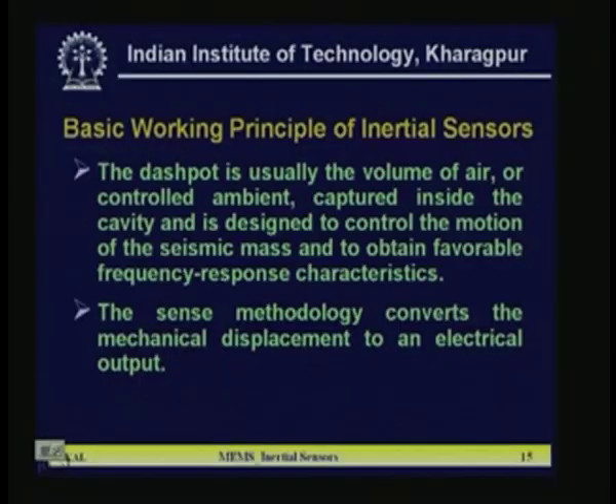And at the same time, this kind of dashpot also determines the frequency response characteristics, because of the natural frequency of that particular structure, and if it resonates, then there is a problem. Resonance means there is a chance of damaging the complete thing, meaning the breaking of the flexure. So, that's why the frequency response is also an important criterion when you are going to design the complete structure. And the last one for the basic principle is the sense methodology. The sense methodology converts the mechanical displacement to an electrical output. Whether it is a gyro or the acceleration sensor, some mechanical displacement will be there, and that has to be converted into electrical output.